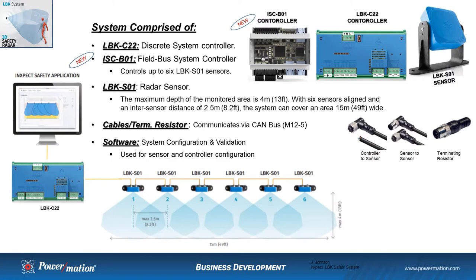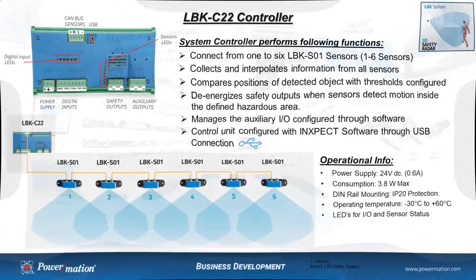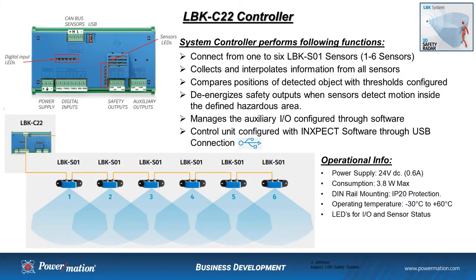With this system, you can connect from one to a maximum of six sensors per controller. The controller collects and interpolates the reflective signals received from all sensors, and it compares those positions of detected objects with the thresholds configured by the users. The controller de-energizes the safe output when one of the sensors detects motion inside the defined hazardous area. System configuration is done through the Inxpect software, and that configuration file is then downloaded to the controller through a USB connection. The system also manages all the I/O configured by the user.